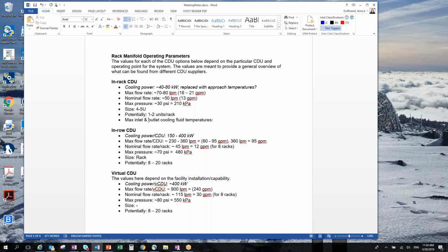So, cooling fluid temperatures—that would depend on your primary site, right? Yes, it depends on your cooling temperature. It depends on whether you want to go all the way to W4 and then take the approach temperatures and determine how much delta T across the coolant loop in the IT gear itself. You may come up with a maximum outlet temperature based on that. But is the maximum outlet temperature here about what the CDU components can deal with?